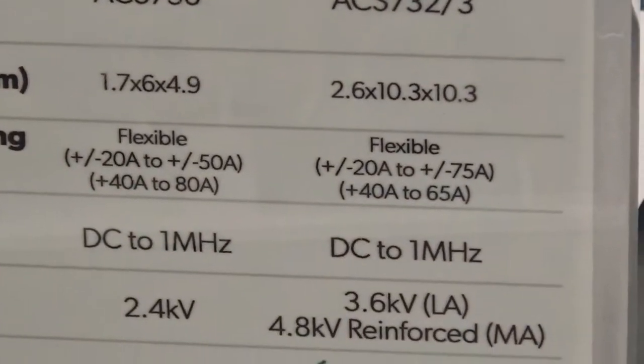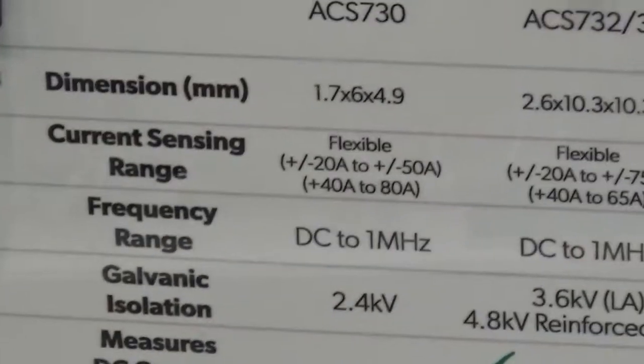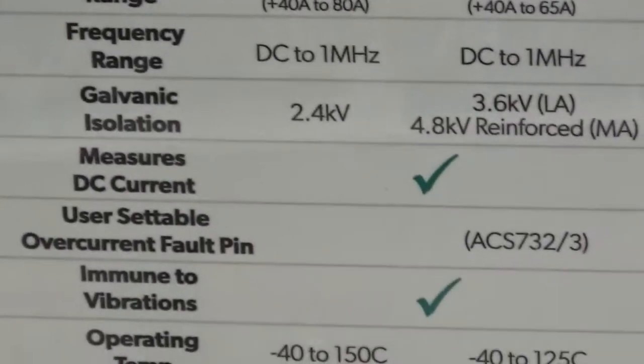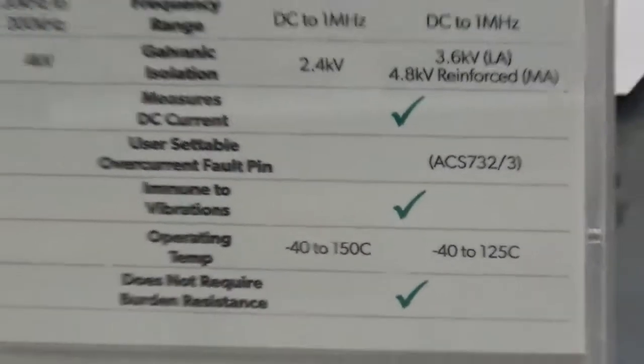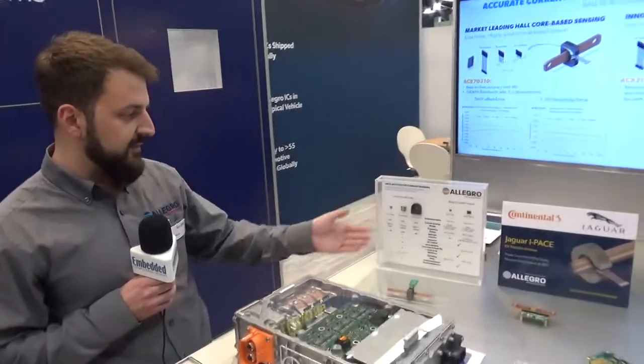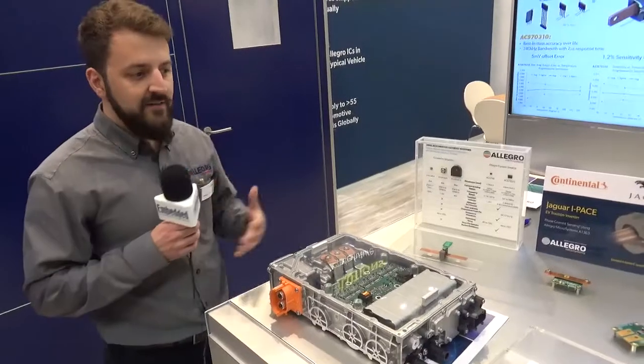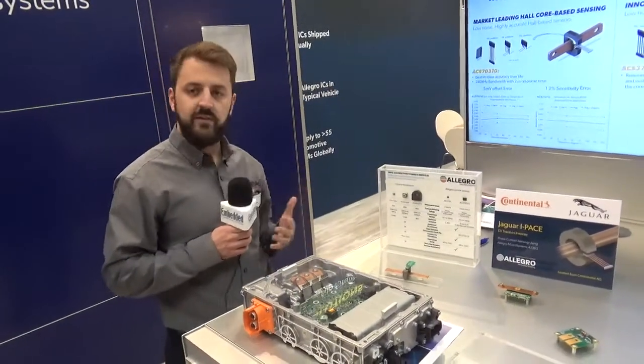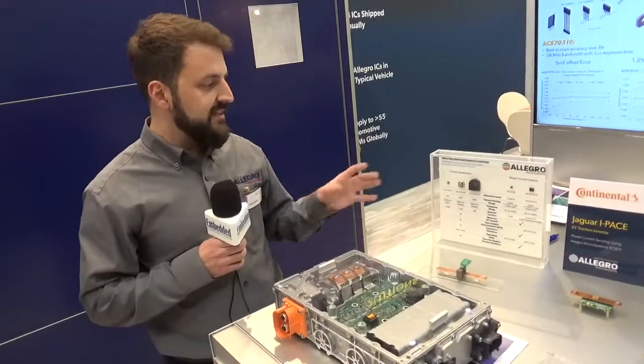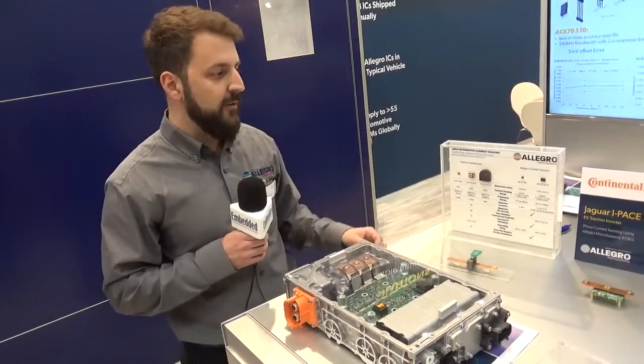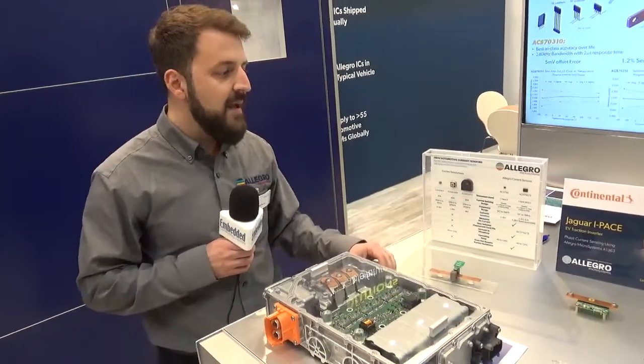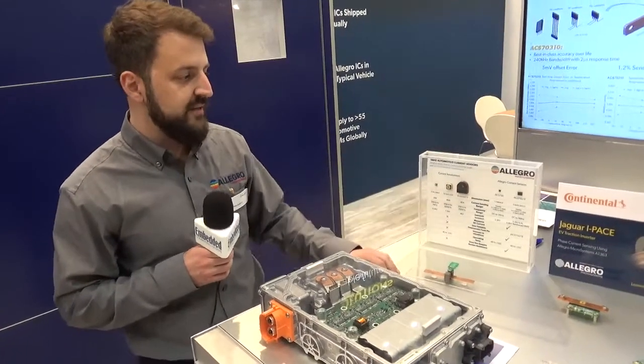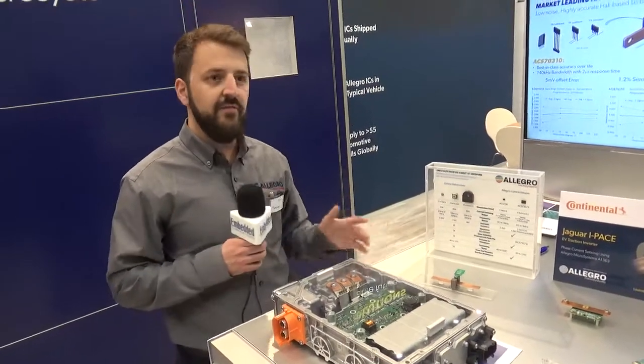If you were to try to have a modular system to measure down to 20 amps or up to 80 amps using a current transformer, you might have to plan for different footprints and different PCBs. If your customer at the last minute says, I have a 40 amp design but this application requires more current, you don't need to respin your board for a new current transformer. Allegro offers many gain options for the 732, 733 device, and we definitely have a gain option that would fit your needs.